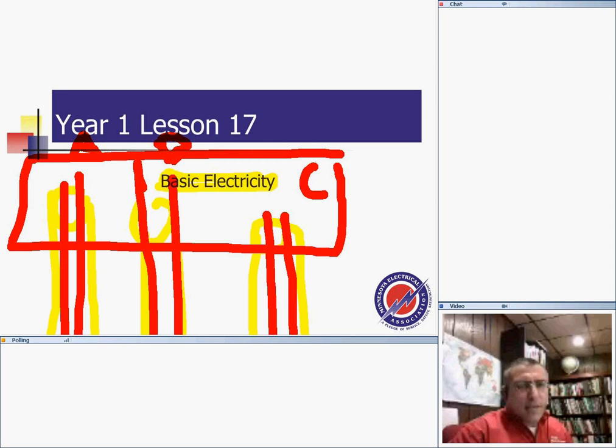THWN-2 conductors have a wet location temperature rating. THWN-2, guys, is rated for 90 degrees, regardless of the location, wet or dry. That's probably why it confused some of you. For the exam, THWN-2 is for wet and dry locations, 90 degrees. Which cable whose type identification is suitable for direct burial? UF, yes. USE, yes. XHHW, yes. Generally speaking you cannot bury a cable unless it is listed. Stop me or chat if you have any question about that one.